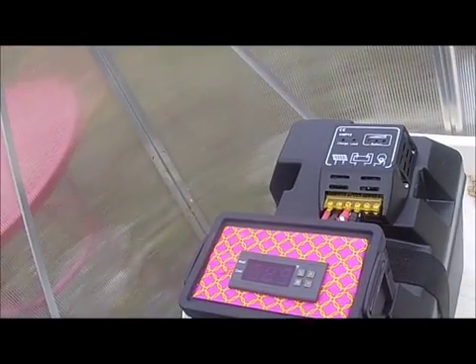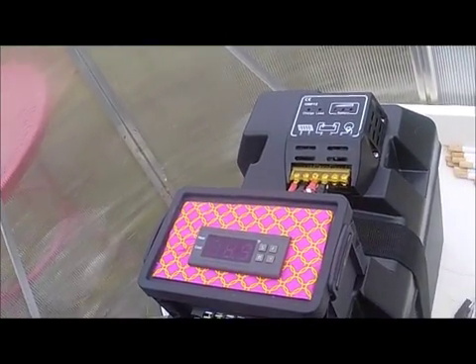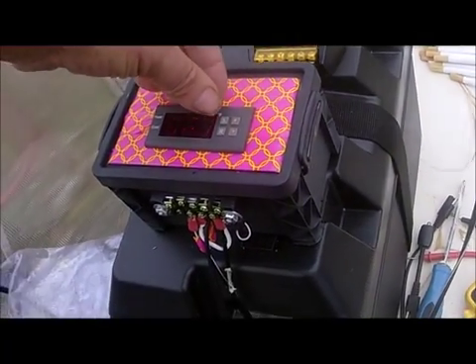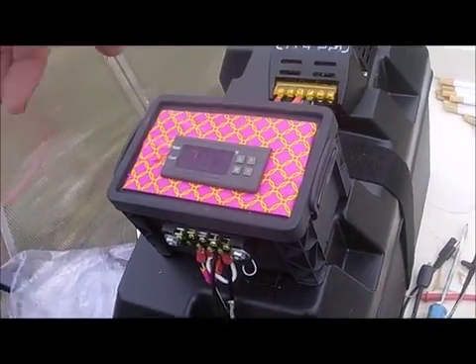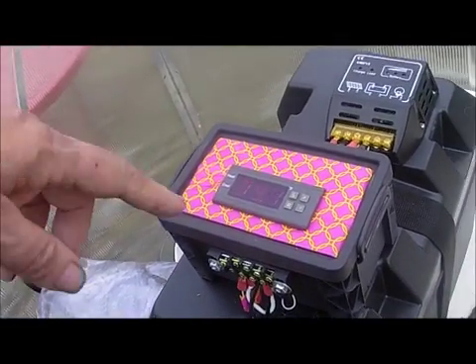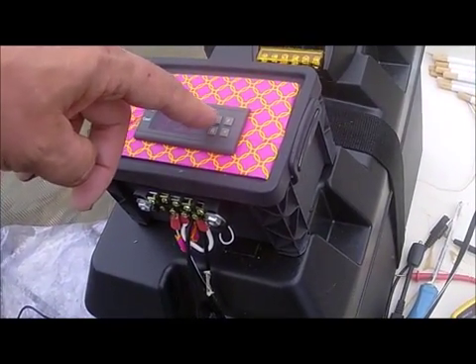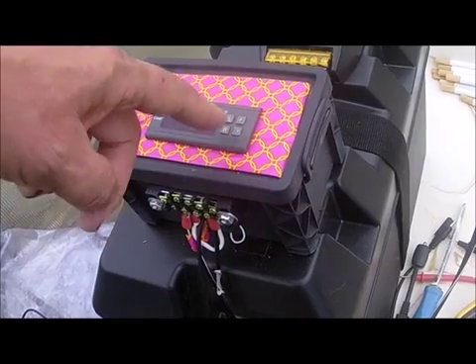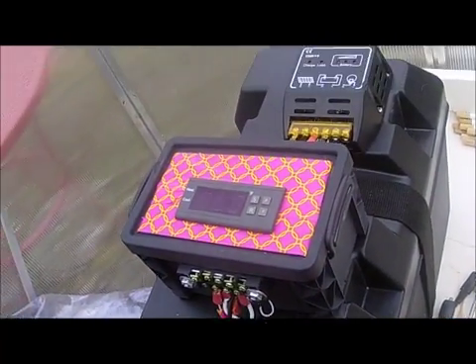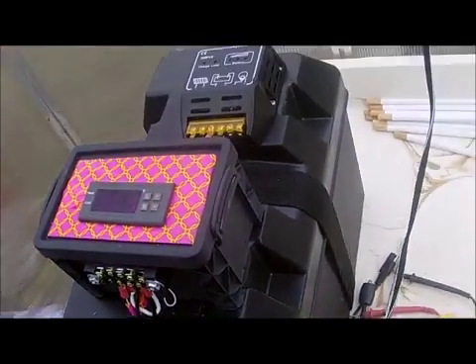If you ever get one of these — they're hard to figure out with the Chinese instructions. In order to set your temperature: press the Set button with the top left button, then press the buttons up and down to your temperature. We're at 79 now. I'm setting for cool. Basically, hold down Set for six seconds and switch it over to cool by pressing Set again. Press R. So press S to set your temperature, go up and down, then press R.